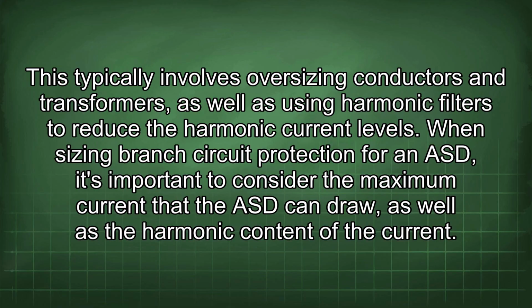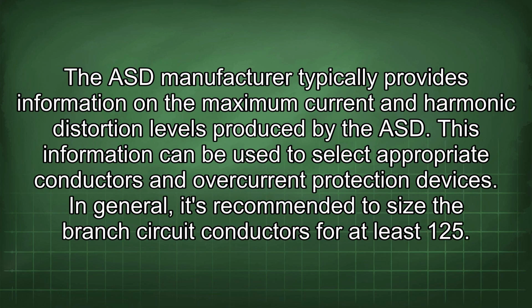When sizing branch circuit protection for an ASD, it's important to consider the maximum current that the ASD can draw, as well as the harmonic content of the current. The ASD manufacturer typically provides information on the maximum current and harmonic distortion levels produced by the ASD. This information can be used to select appropriate conductors and overcurrent protection devices.